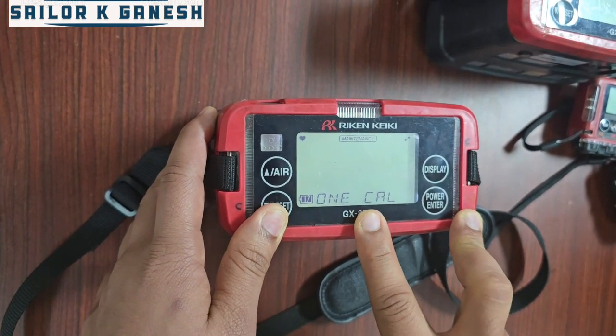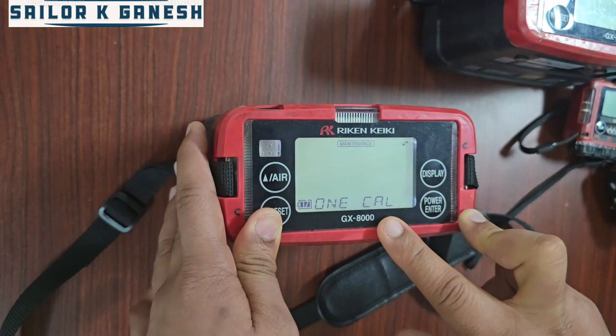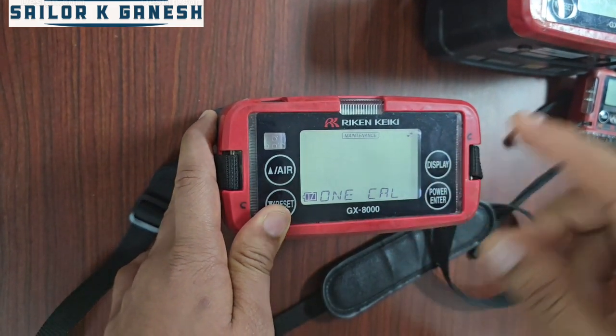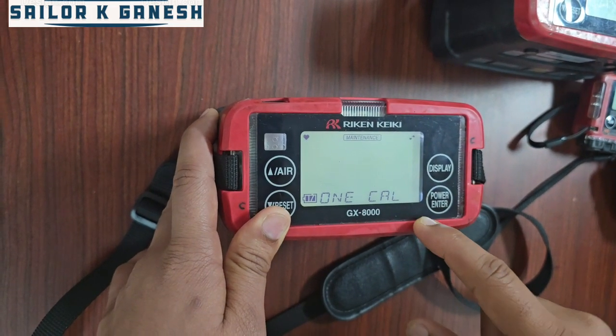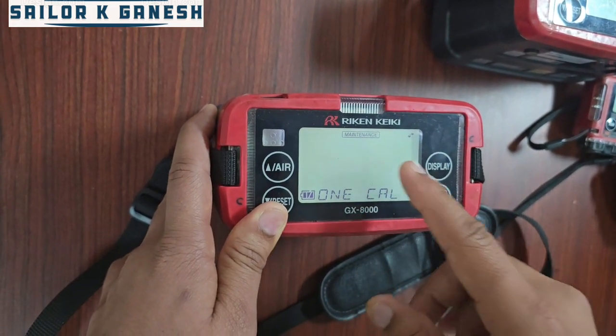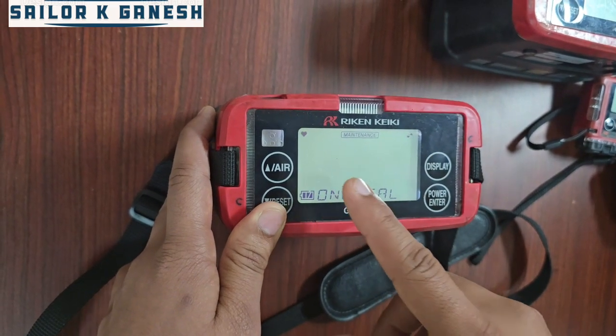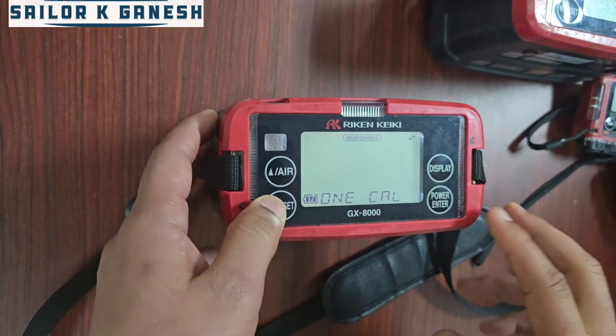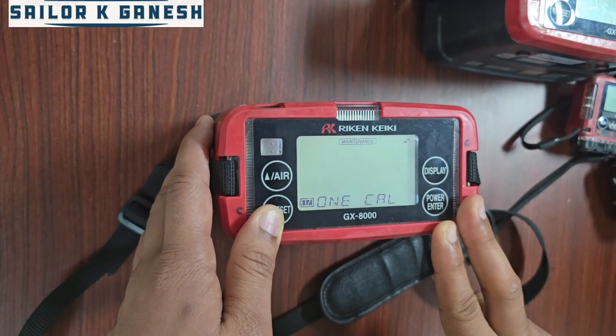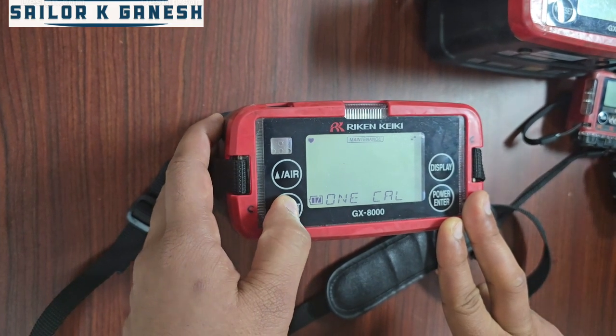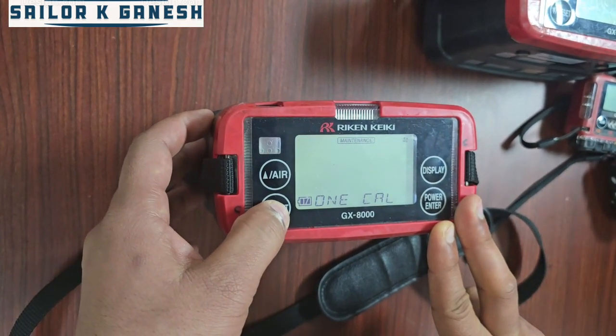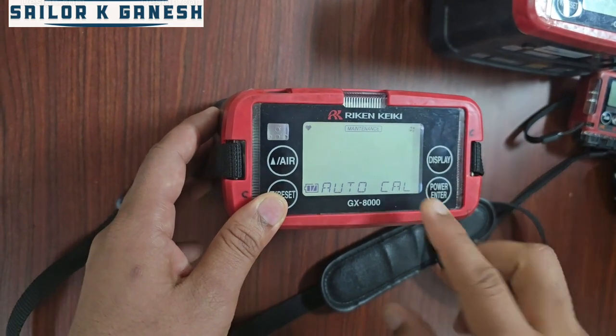Here we have one cal. If you don't have multi-gas bottles on board, then you can do one-by-one calibration for all the sensors you have inside, like CO, O2, LEL, and H2S. We will go for all the gases together. So we have the auto cal function also here. We go to the next step. Okay, this is the auto cal.